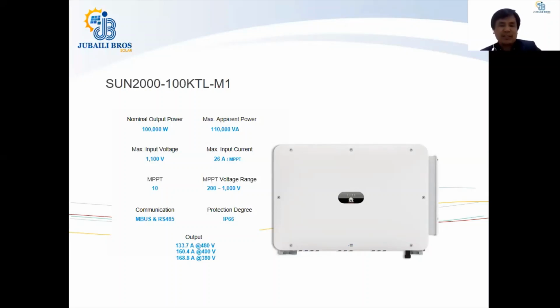In communication with these inverters, we have introduced the MBUS, which was commonly known as the PLC communication previously. The PLC communication happens through the power cables. We will speak again about it in the later slides. Regarding the RS485, this has been very commonly used in the previous inverters as well. With the protection degree, again, we have now increased the protection of the inverter to IP66. Previously, our inverter was IP65. It has been made IP66 to make it adaptable for flooding PV plants.